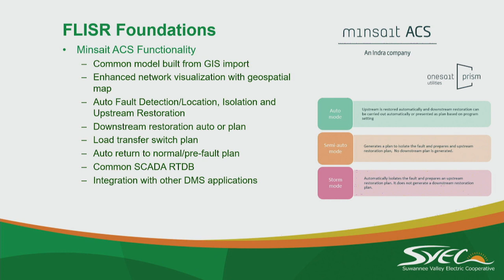Outside of that, these are the following constraints that FLISR can observe. When it does those switch plans, it can check high and low voltage limits at each node. It can do thermal limits based on wire sizes in your table. It can look at loading limits on switches and breakers to make sure you're not going to overload a part of your line when you do the switching.